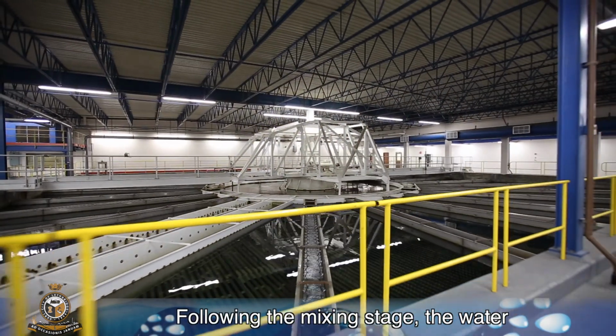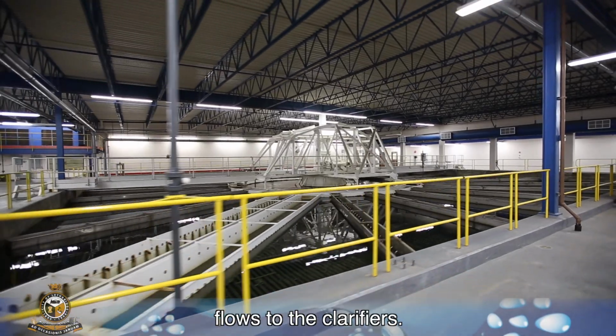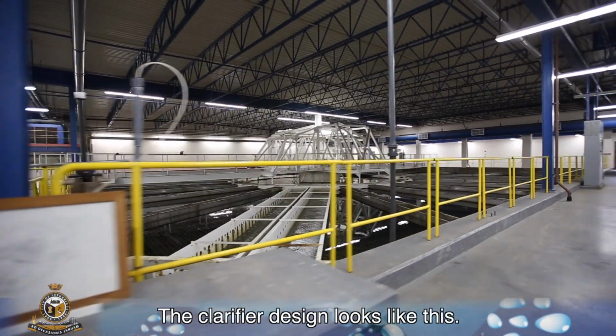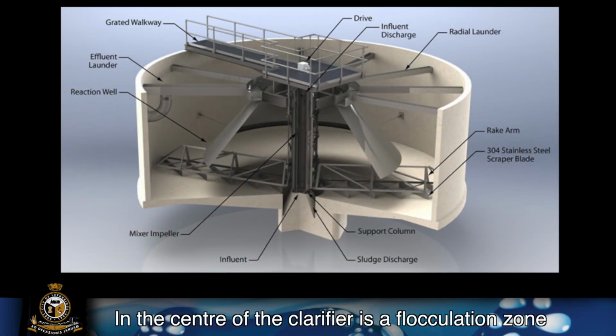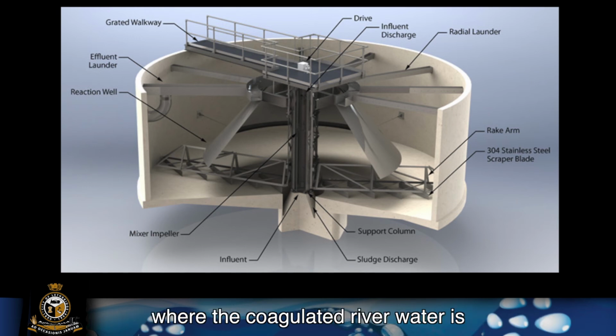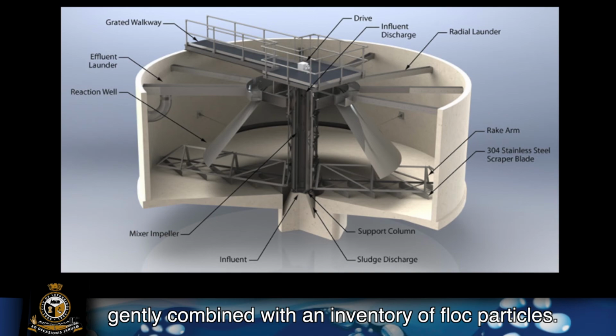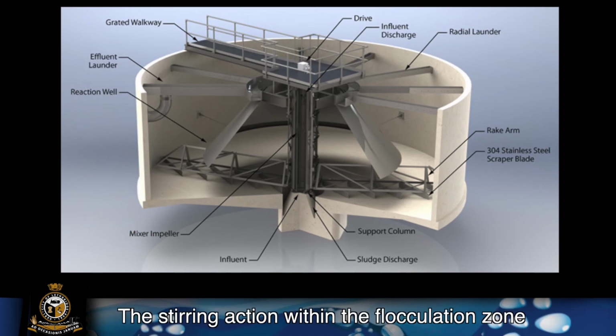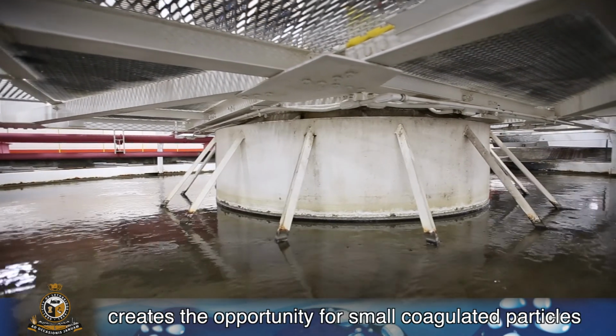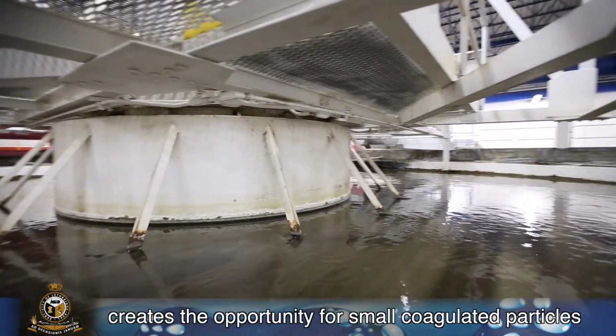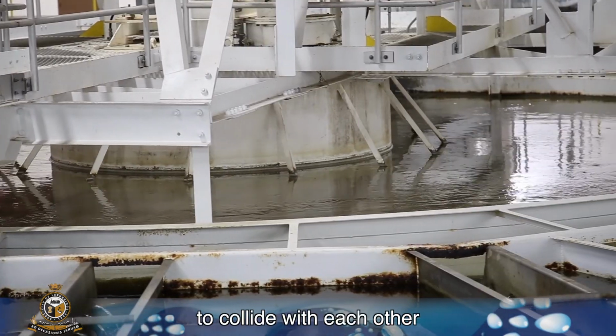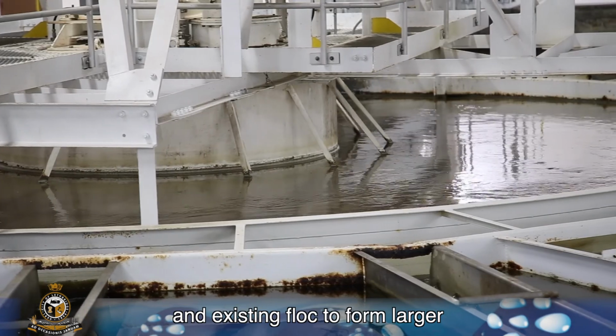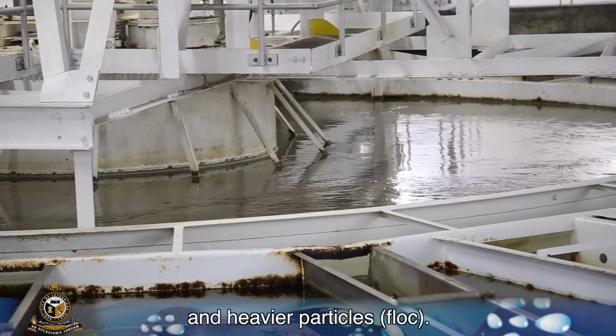Following the mixing stage, the water flows to the clarifiers. The clarifier design looks like this. In the center of the clarifier is a flocculation zone, where the coagulated river water is gently combined with an inventory of floc particles. The stirring action within the flocculation zone creates the opportunity for small, coagulated particles to collide with each other, and existing floc to form larger and heavier particles, floc.